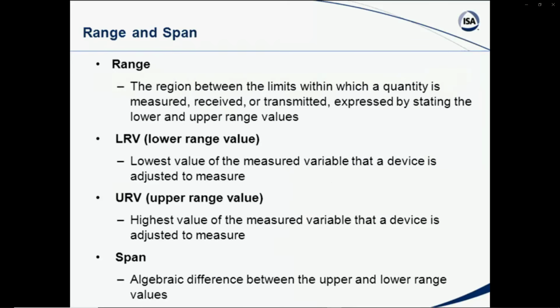And now, talking about transmitters in general, let's look at some terminology that could come into play not only with some of the questions on the exam, but you might have to understand these terms if you read a question about some other part of the exam, some other topic area in the exam. So we need to have some commonality here. First, we talk many times about an LRV and a URV for a transmitter. The LRV being the lower range value, or the lowest value of that measured variable that the device is adjusted to measure. And just along the same lines, the upper range value, the URV, is the highest value of the measured variable that a device is adjusted to measure.